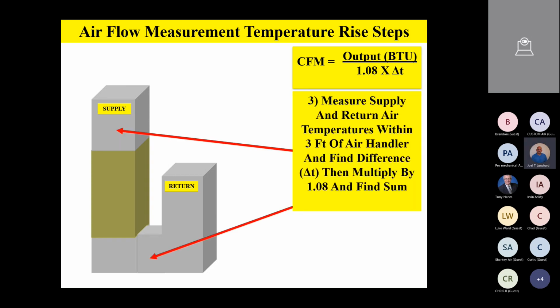Step number three, you're going to measure the supply air temperature and the return air temperature. We recommend doing this within about 3 feet of the air handler, because you don't want the heat strips cooking directly against your temperature probe. So go about 3 feet down the supply duct, and if you can't do it that way, then go to your very first supply register for the supply temperature. Anyway, try to be about 3 feet from the air handler on the supply temperature reading, because again, the heat strips can give off radiant energy and throw off the temperature probe a little bit.